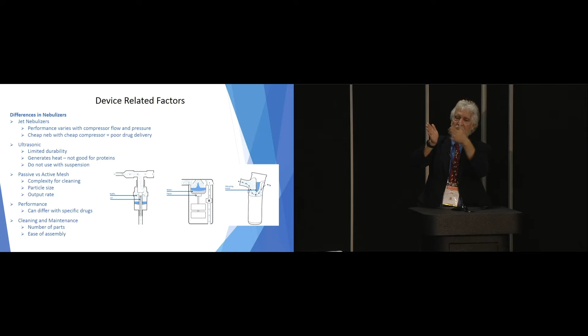Vibrating mesh doesn't foul as often. It's a little bit more dependable in my mind. But the big issue is the performance. So if you have a jet nebulizer and you have a very viscous drug, it's pretty similar. If you have a mesh nebulizer and it's viscous, higher viscosity can reduce the output rate and eventually slow it down. Most of the drugs that we prescribe today for aerosol aren't high enough viscosity to make a difference. So the performance can really differ with specific drugs, and cleaning and maintenance is really an issue.